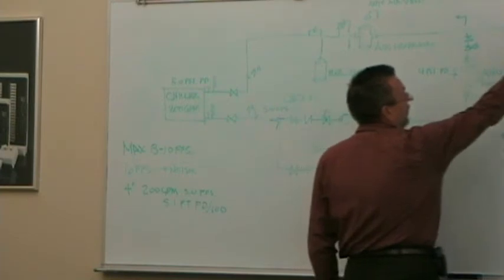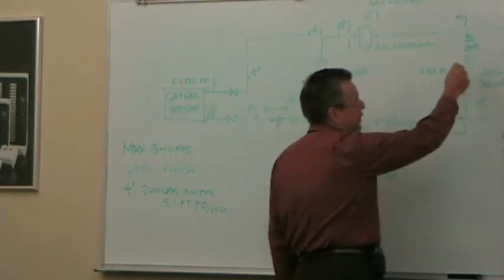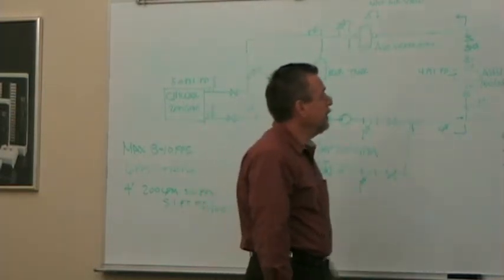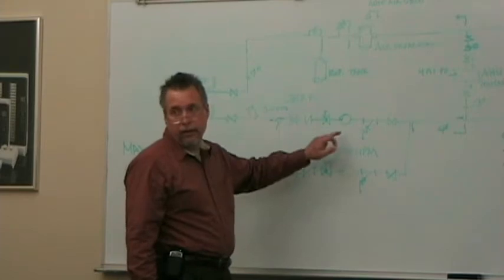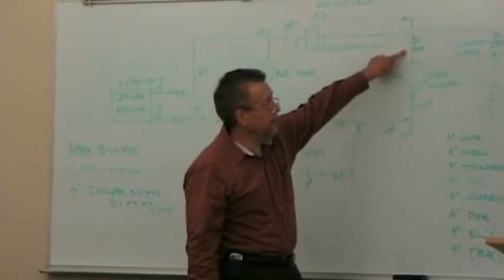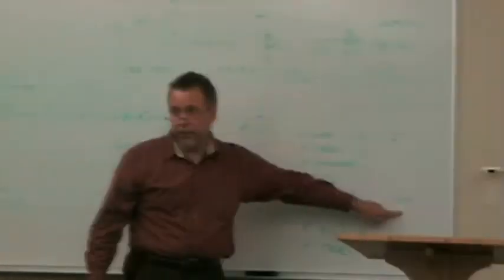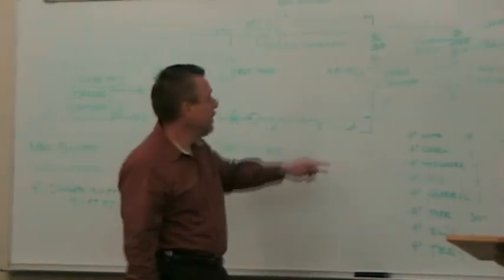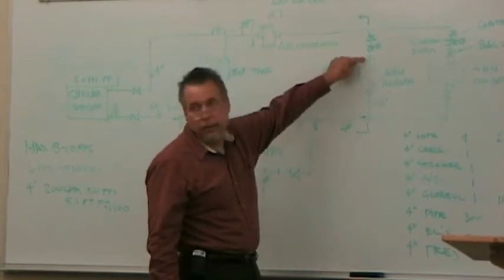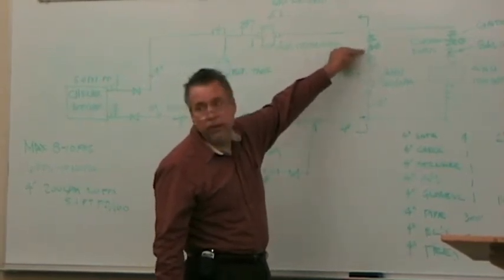Okay. Now, the balancing valve is what I want to use here to set the flows through the coils. It's the initial startup of the job. In a variable volume application, we talked about having very critically sized control valves and eliminating that, because that's energy dollars. That's pressure drop, that's costing me money to operate. So in a variable volume application, I would argue we don't need this, because I'm going to furnish a good enough valve that under control will balance the entire system.